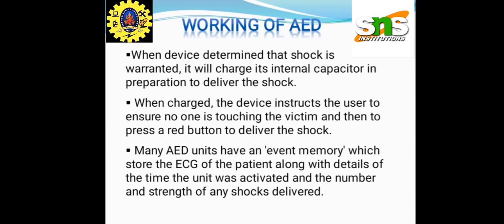When the device determines that a shock is warranted, it will charge its internal capacitor in preparation to deliver the shock. When charged, the device instructs the user to ensure nobody is touching the victim and then to press a red button to deliver the shock.